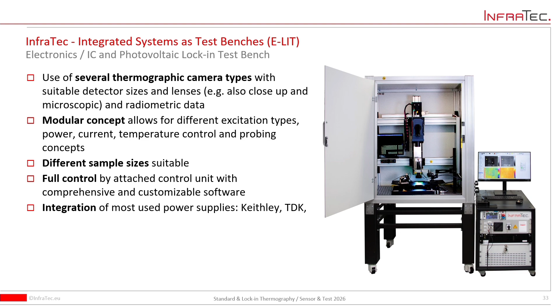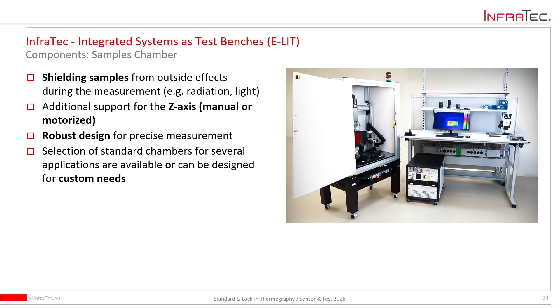Okay? So the chambers are required for preventing everything inside from environmental impact, due to moving people, due to other guys in the room, and so on, so that the environment will be stable during the lock-in process. Okay? And what we can offer as well, we can offer an XY table, manual or motorized. Let me say, if the chip is too large, and if you want to use a microscope lens, the image will be very small. And for the chip surface, sometimes you will need to create a lot of images, and then you need a tool called stitching for recombining the single images into one big resulting image.